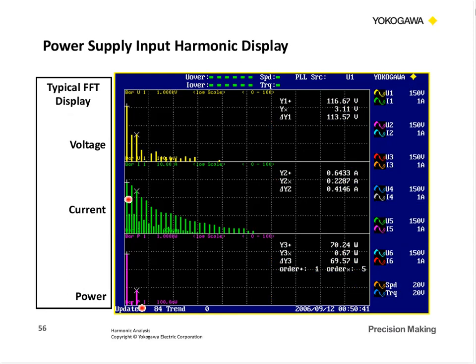All right, look, we've got a lot of harmonics out here on the current side. It decays pretty evenly, doesn't it? And then we've got voltage that drops off pretty quick. This is very low. This is a log scale in amplitude, so this voltage is very, very small. And so some of these power harmonics just don't even show up because of that low voltage. We can see we got a good measurement at the fundamental, and still some good power measurement at the 5th order. And the rest of them drop off pretty quick. They're gone. They don't even show up.